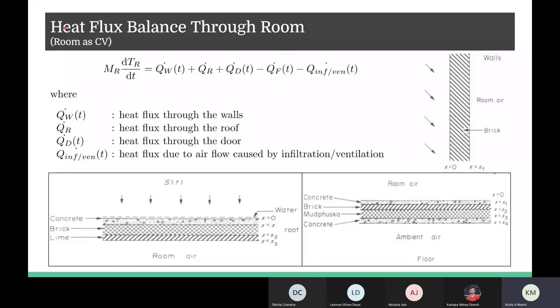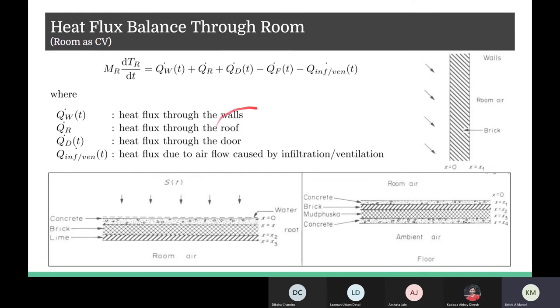Now we will see how the heat flux balance works through the room. Heat flux comes through the walls, the roof, the door, and infiltration/ventilation — air coming in and going out. Through the wall, roof, and door, the major forms of heat transfer are convection between the air and the layers of the wall, and then conduction within the walls, roofs, and doors. One more important form of heat transfer is the solar radiation incident on the roof.